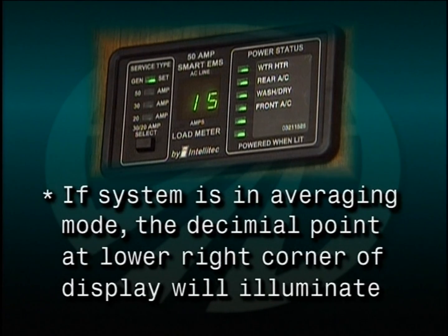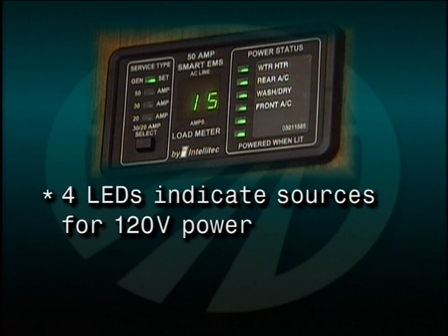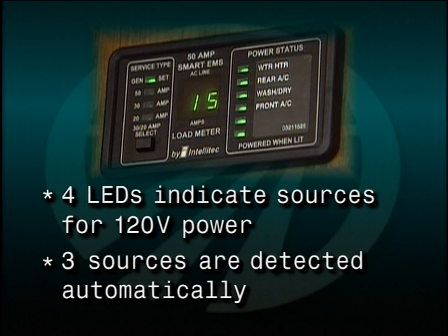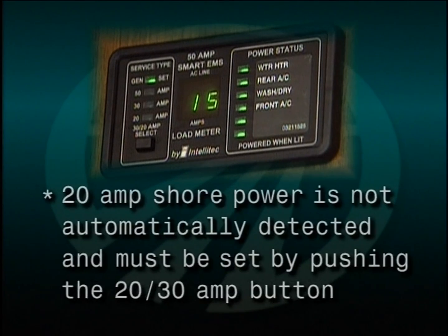If the system is in the averaging mode, the decimal point at the lower right corner of the load meter display on the display panel will illuminate. 4 service type LEDs indicate the source for the 120 volt power. 3 of these sources are automatically detected and indicated by the EMS: the generator, 50 amp shore power, 30 amp shore power. The 20 amp shore power is not automatically detected and must be manually set by pushing the 20-30 amp select button to match the service.